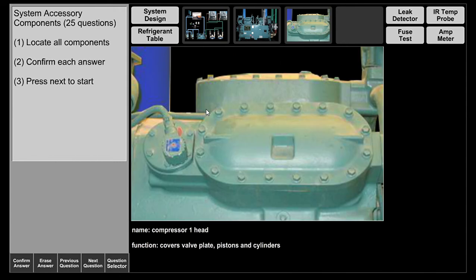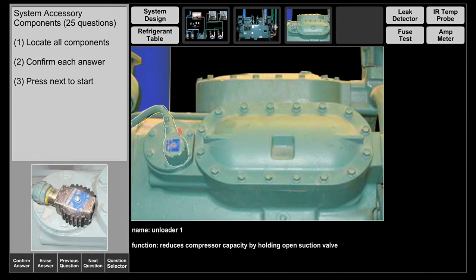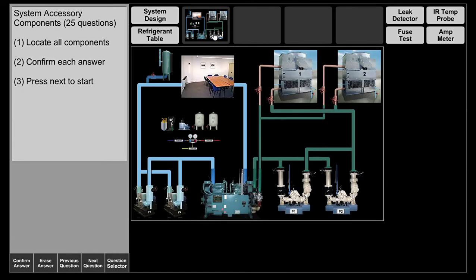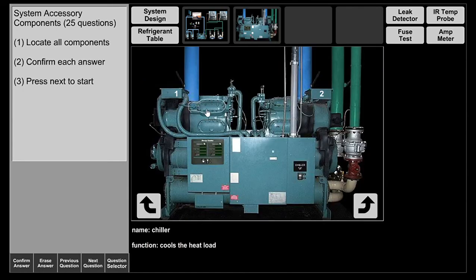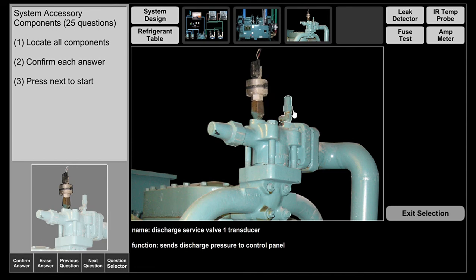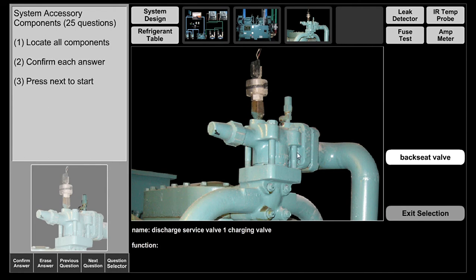As the vapor goes through the pistons it gets compressed into a high temperature, high pressure superheated vapor. The compressor also has an unloader, which reduces compressive capacity by holding a suction valve open. When the room load is satisfied and you don't need maximum cooling, the unloader holds the suction valve open so the piston doesn't compress that vapor — the system continues operating without overcooling the space. On the discharge side you have the discharge service valve, high-side transducer, and charging valve; high pressure, high temperature superheated vapor exits.